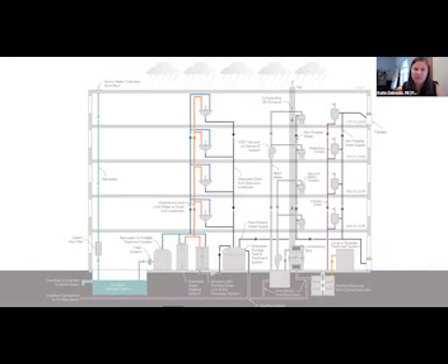This is really one of the innovative pieces for us on the plumbing side: combining the idea of a vacuum flush system with composting toilets. It helped us address a few issues we'd seen in other living building projects pursuing the water petal, and it allowed us to decouple the system from gravity. Most composting systems rely on gravity to move material through the system, but this allowed us to have all of our compost bins in the main mechanical room tied to a general system, not simply tied to a single fixture. So if one water closet or toilet gets more use than others, it doesn't necessarily mean the overall composting bin system is out of balance.